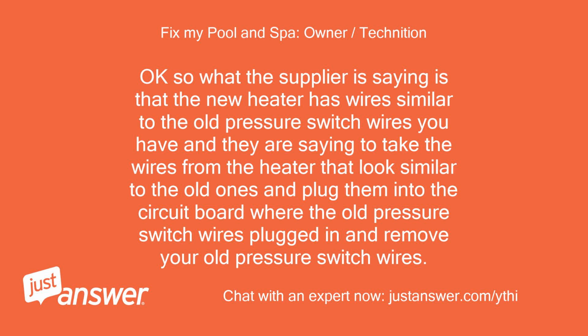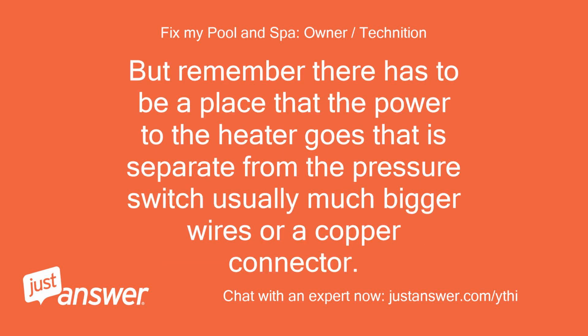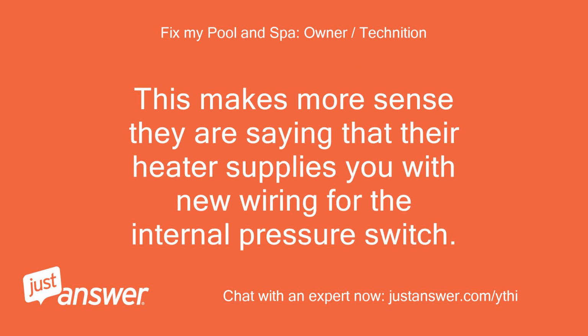Okay, so what the supplier is saying is that the new heater has wires similar to the old pressure switch wires you have, and they are saying to take the wires from the heater that look similar to the old ones and plug them into the circuit board where the old pressure switch wires plugged in, and remove your old pressure switch wires. But remember, there has to be a place that the power to the heater goes that is separate from the pressure switch, usually much bigger wires or a copper connector. This makes more sense. They are saying that their heater supplies you with new wiring for the internal pressure switch.